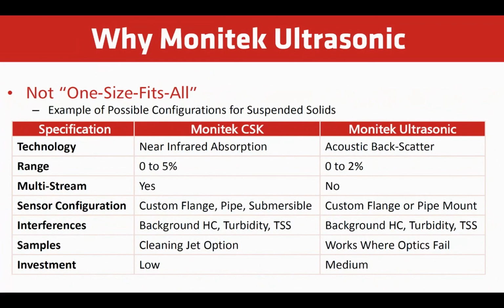meaning it works on acoustic backscatter, but we also offer a near infrared absorption probe for different ranges, depending on customer requirements. If we had to do 0 to 2%, we could choose either an ultrasonic or a Monitek CSK. There are pros and cons to both. The CSK is multi-streamable: you can add up to 4 of them on one controller, whereas on the ultrasonic you cannot. It's only one sensor per transmitter. Again, both are completely customizable for the mounting or customer requirements. Same types of interferences again. An optical or the Monitek CSK requires a cleaning jet, whereas the ultrasonic does not.